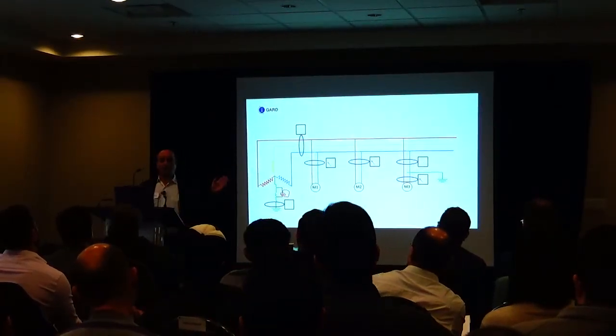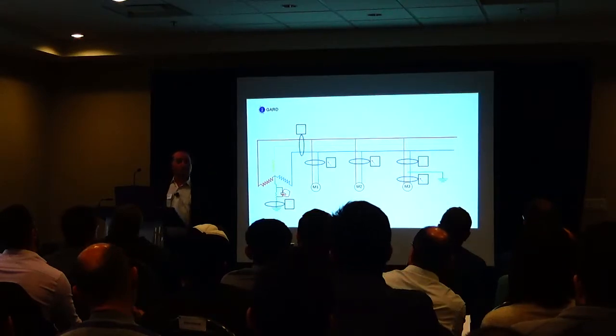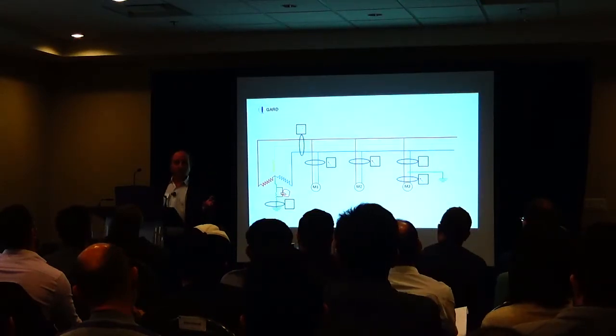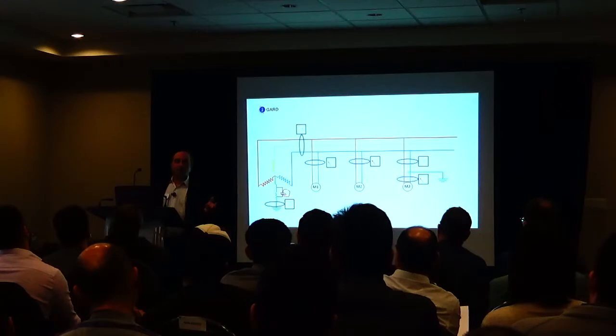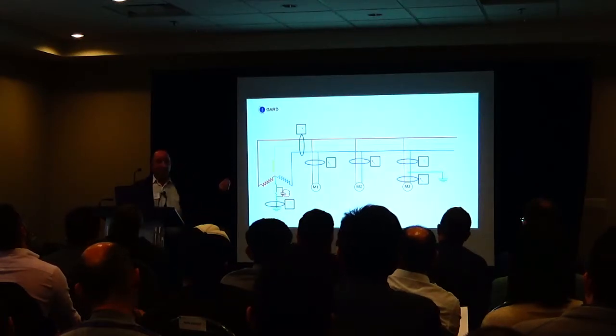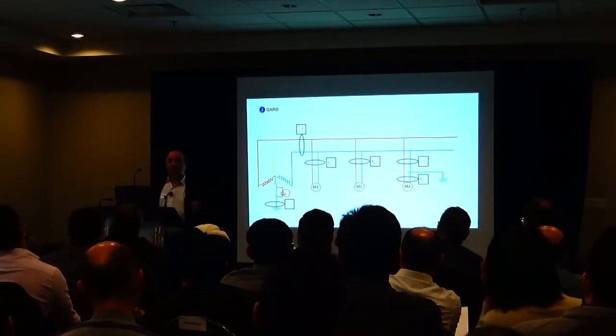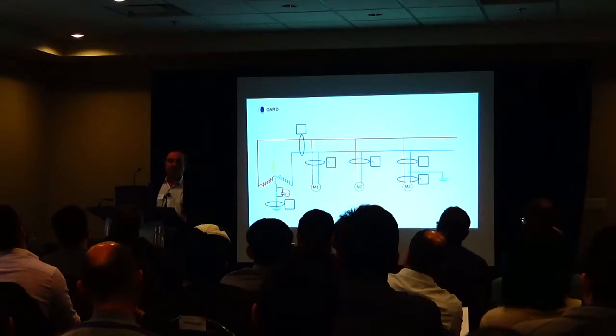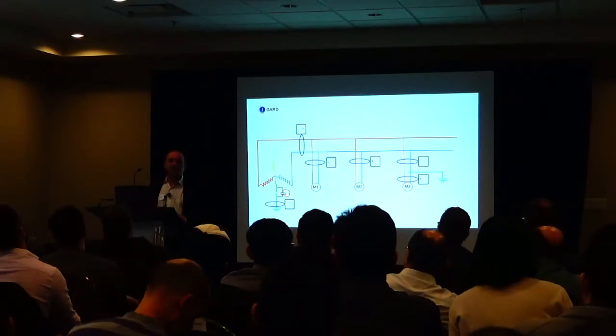You don't have a neutral, so you don't have the distributed neutral. You don't have 3-phase 4-wire switchgear. You have 3-wire distribution. You can actually take out the G function of all your breakers, and you can probably save a lot of money by just using a resistance grounded system.